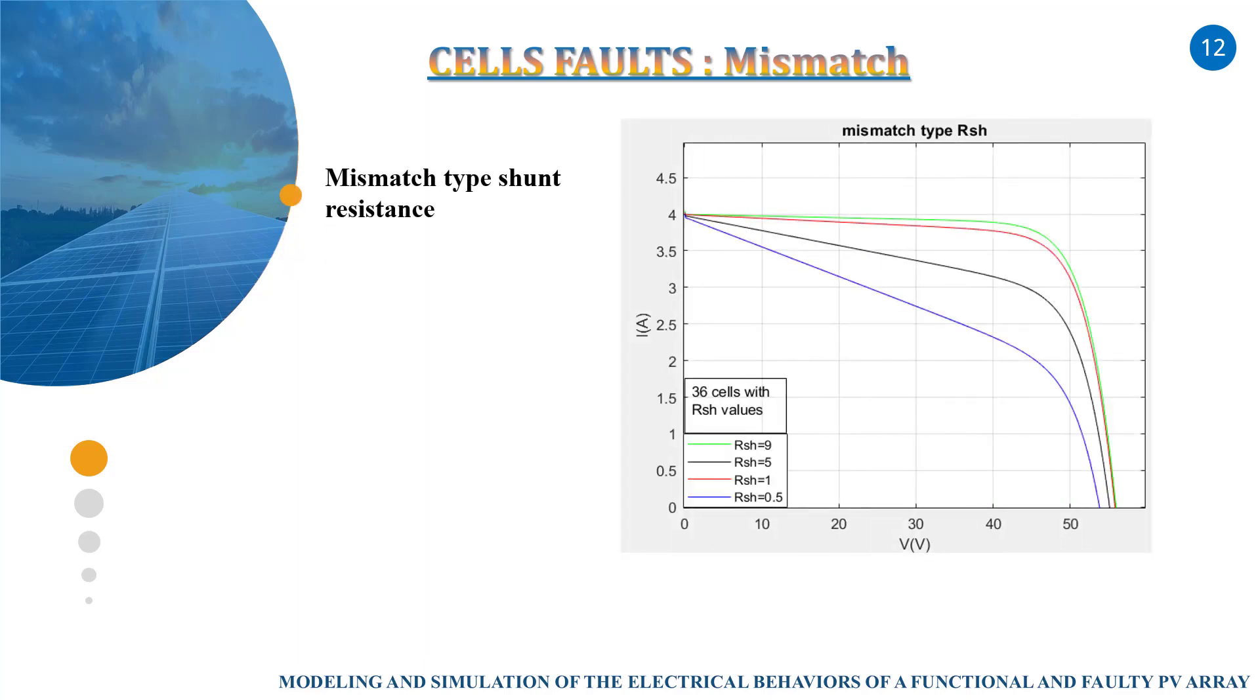We begin by cell fault. We have the mismatch. The mismatch is the most frequent fault caused by grouping cells with non-identical current voltage characteristics. In this figure, we have 36 cells with a mismatch shunt resistance.